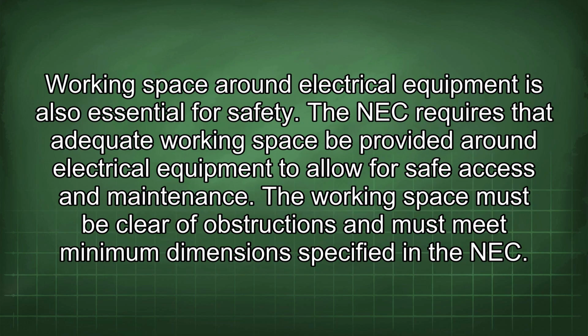Working space around electrical equipment is also essential for safety. The NEC requires that adequate working space be provided around electrical equipment to allow for safe access and maintenance. The working space must be clear of obstructions and must meet minimum dimensions specified in the NEC.